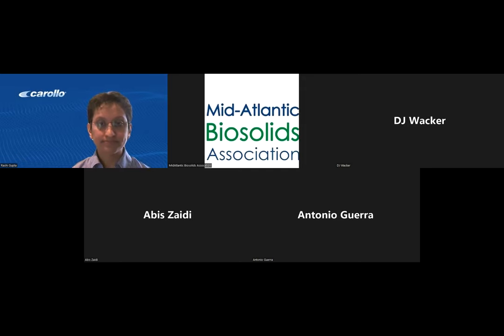All right, thank you. And then there's another one directed at you, and that says, how does the system know if polymer is not being overdosed? So basically, the operator will be able to identify an overdose of polymer, mainly because one of the consequences will be extreme foaming of the centrate. So in the measurement analyzer that looks at the centrate stream, there is a foaming index, which gives a data stream back to the operator, indicating that the foaming is actually more than it was maybe an hour ago.